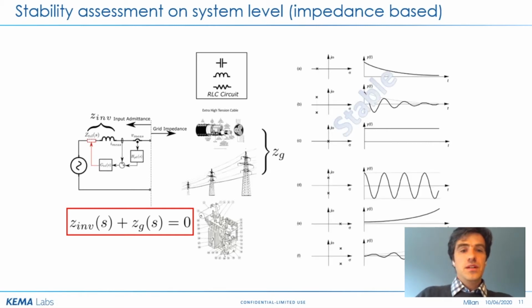If you have a cable connection or a transformer connection at the higher frequency components, which become significant for converters, you also need to model these components in that frequency range to be able to predict and simulate these aspects as well. This means your whole exercise becomes more complex, but it needs to be realistic, to avoid any nasty surprises when you go into real life and deploy such systems. So this is the message here: more homework to be done when looking into a power electronics dominant grid situation than might have been necessary before.